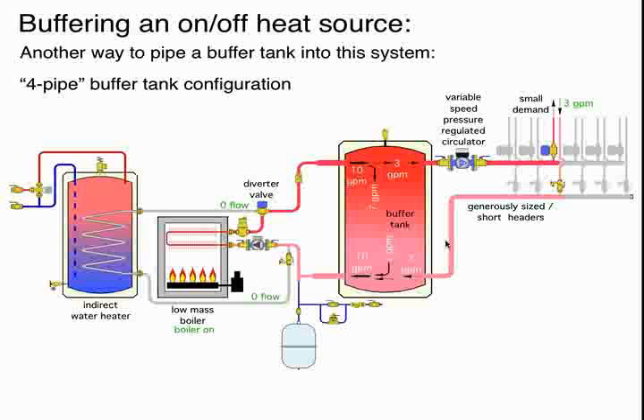On this particular system? Mm-hmm. Probably not, because think of the indirect water heater as essentially self-buffering just because of the volume of water stored in the tank. It's a self-buffering load. So it's actually a good point. You really don't want to, in my opinion, heat up a dedicated buffer tank just to provide heat to an indirect water heater, because now you're maintaining 2 tanks and you're going to experience higher standby heat loss. So good point. Specifically, treat that high-mass domestic water load as self-buffering, and then everything on the space heating side goes through the other buffer tank.